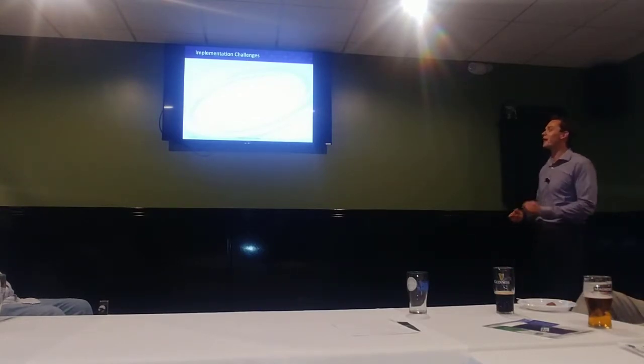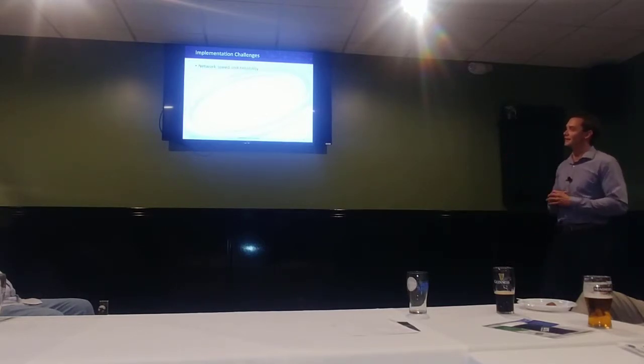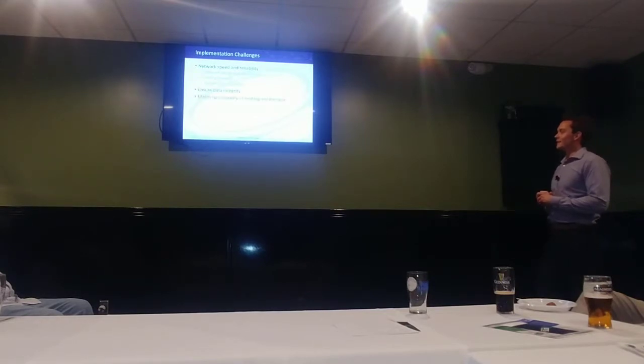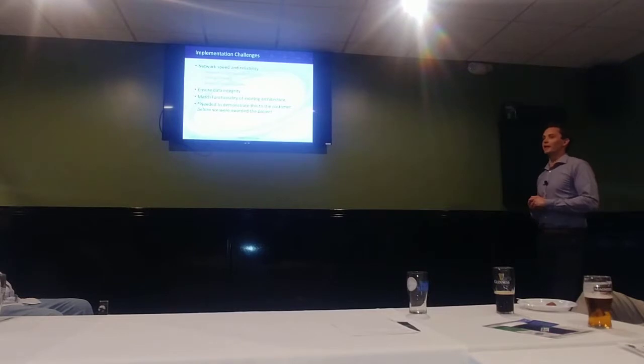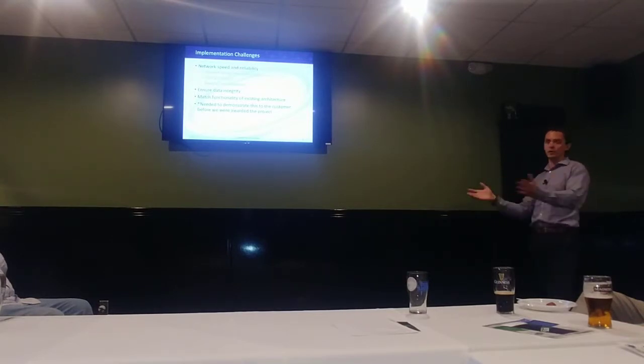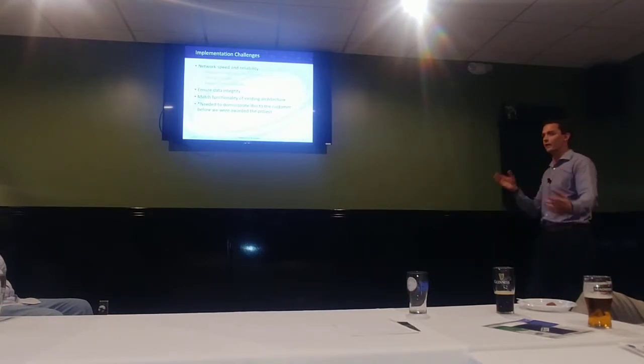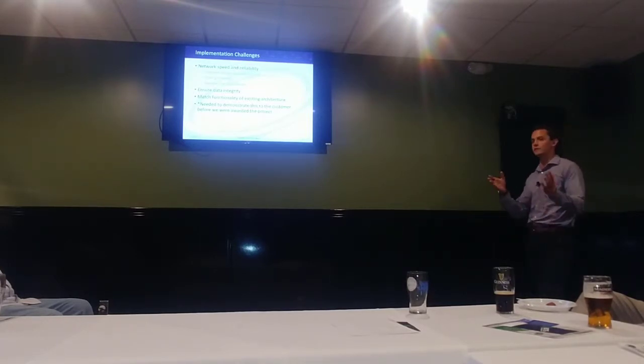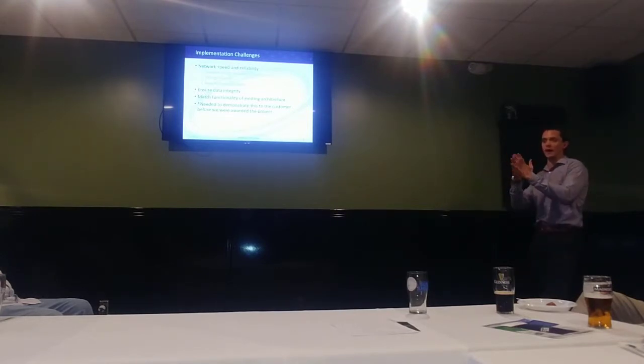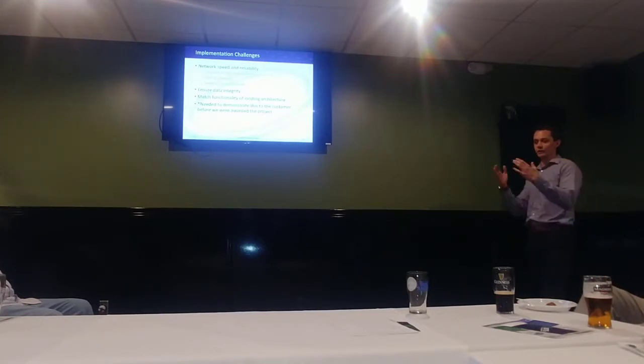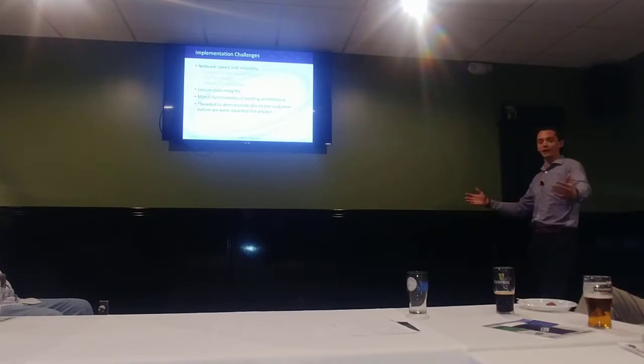Next slide. So I probably made that sound really easy. It was actually quite a challenge to do this. In doing this, network speed and reliability are obviously paramount. They're paramount when you're designing a regular BAS network, where you consider how many devices you put in an MSTP loop and how long your IP runs, and that's enough of a challenge on a regular BAS. But when you talk about integrating all of those protocols into another platform, and then layering that on top, you need to think about it even more. Polling intervals: how often are we going to poll the network from the ProSoft BACnet card standpoint? We have to make sure that we're not overloading the ProSoft cards, and we're not overloading the network at the same time. So we needed to figure out how we're going to put all this together.